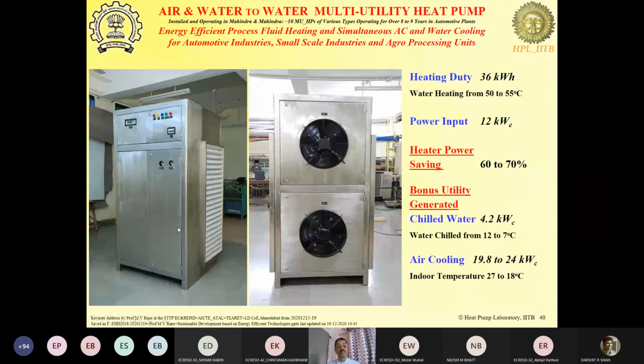So as I said, this was the unit, and after the first unit was deployed, they were happy with the performance. They said, can you reduce the footprint? So we reduced the footprint to just 1 meter by 1 meter in this particular case. And then this was with an 8.3 ton compressor. And then we also were able to deploy a 12 ton compressor in the same footprint with the evaporator stretching up all the way to the top on both sides. Okay. And so this was 36 kilowatt, that was around 55 kilowatt.